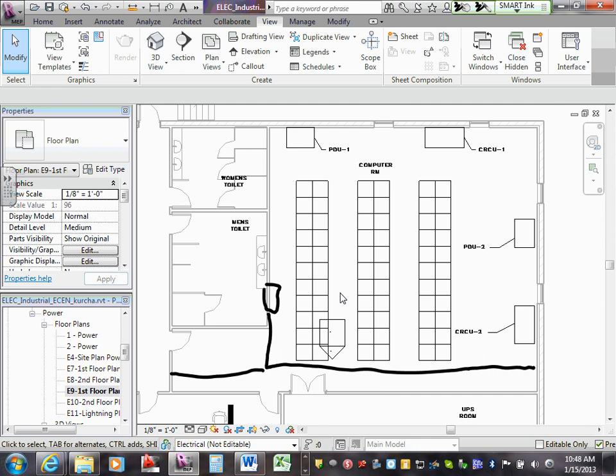It's a special room. It goes raised floor first, and there's computer equipment, and they have their own cooling units. This is computer room cooling, the CRAC unit we call them. See, this is computer room cooling units, very specialized in just pushing cold air right underneath the raised floor to keep the servers cool so they can crunch more numbers. Otherwise, the servers will not function right. They will heat up and fail. So they have a special cooling system just for that particular room.